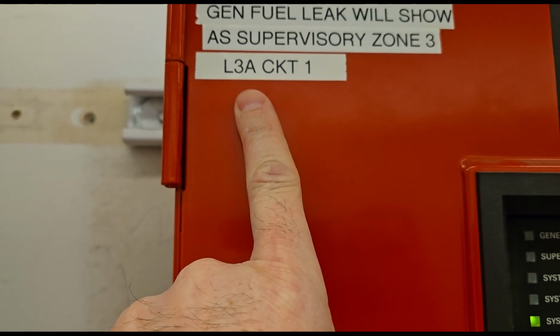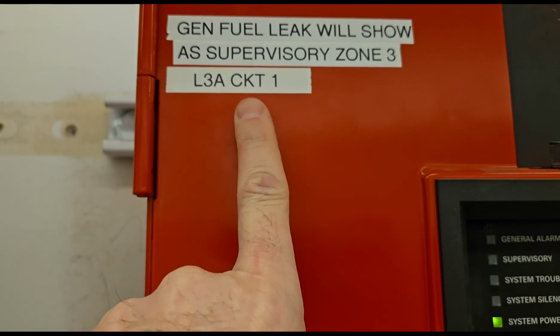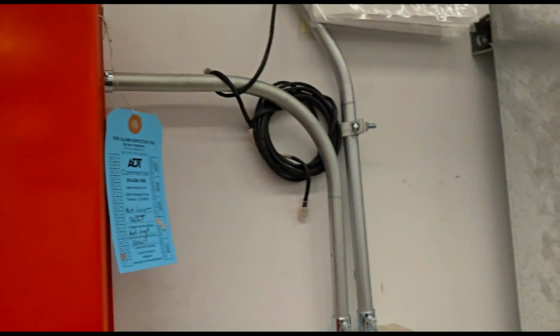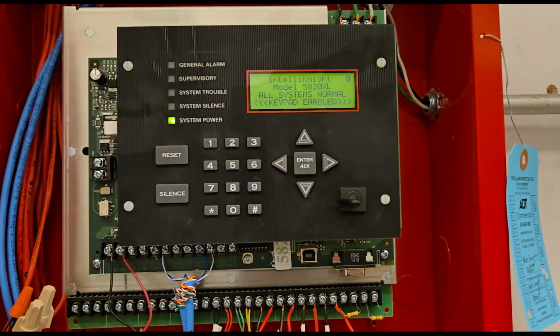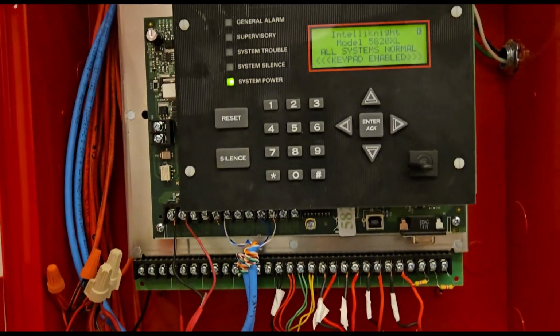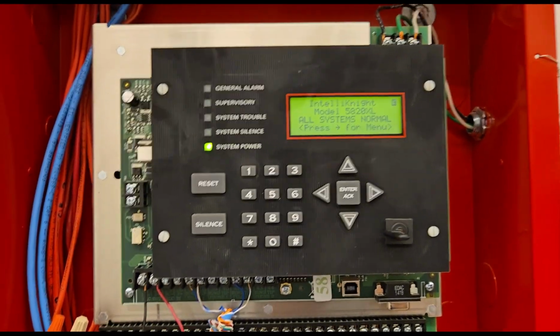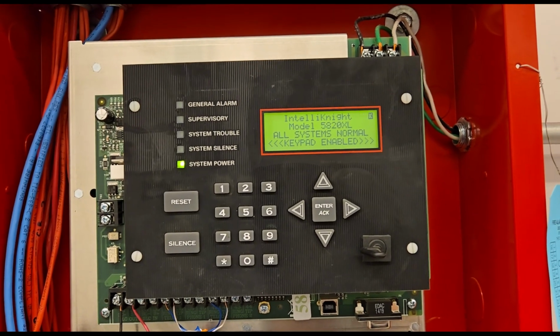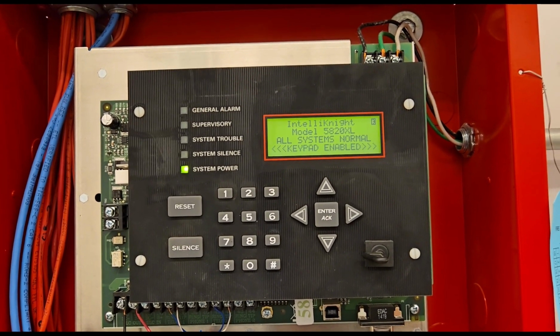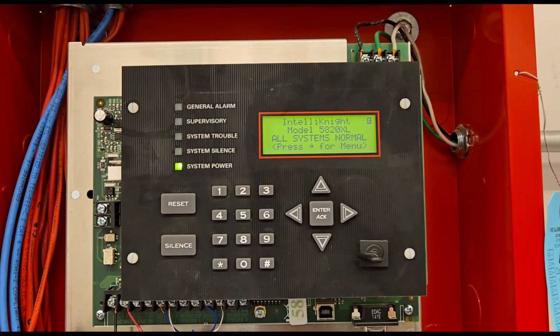We make sure that we have it labeled on the front of the panel so we know where our circuit breaker's at. We have our breaker lock and it's identified, and we measure it with our voltage meter to make sure that it did in fact kill the power. And that is how we do the AC breaker disconnect test for a fire alarm panel.